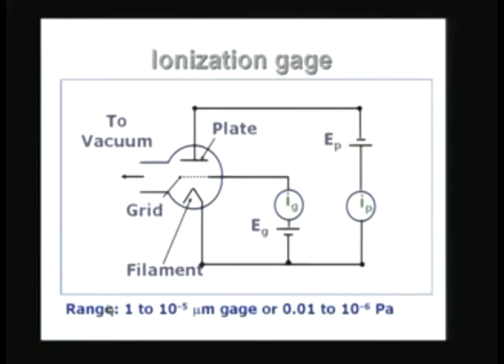The ionization gauge can also be replaced by what is called a Penning gauge. The working principle is the same; the only difference is that in the Penning gauge, the filament is not hot. Instead, a very large potential difference is used, so ionization of the residual gas takes place due to the high electric field near the cathode. So the way ionization takes place is different. The Penning gauge is also called a cold cathode gauge.